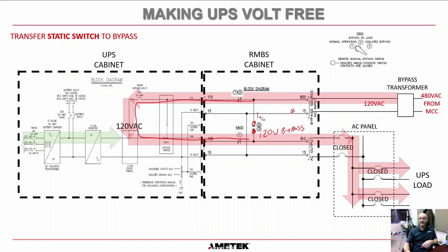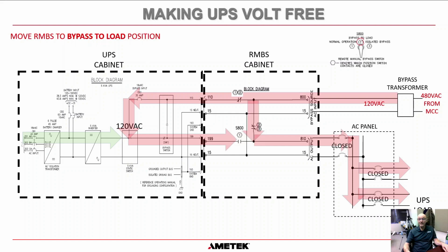So when we go ahead and change the position of that switch to position 2, we make this contact here and then we break this contact here. So that allows us to have a seamless transfer of power. So now power is actually flowing through here, down through that contact and out to the load circuits here. Yes, we do allow bypass to go back into the UPS. That's more for testing purposes. When we're in position 2, the factory trained FSE can go and do some testing if necessary. But in this position, we are now in what we call maintenance or manual bypass. Okay.